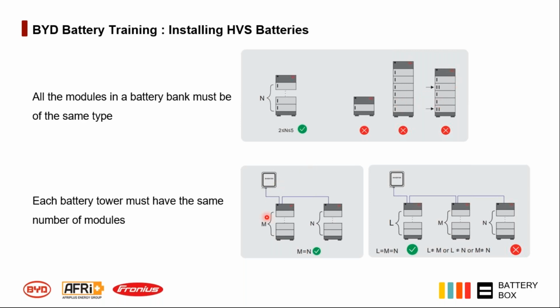And when you are paralleling towers, it's very important to make sure your towers have the same number of modules, because the voltage in your tower is dependent on the number of modules in it. So for instance, if you've got a tower of 4 modules, it'll be about 400 volts. So it would be difficult to put a battery of 300 volts in parallel with that. You'd have to have the same voltage on your towers. So it is very, very important to have the same number of modules in each tower when paralleling.